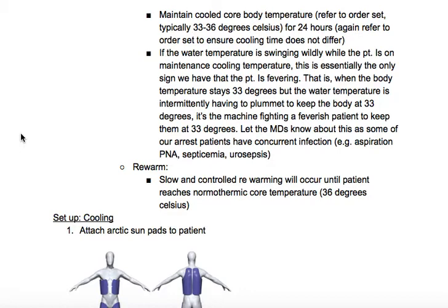And then this was another small note that Chris also made I thought was really interesting. Because the patient is febrile, or could be febrile, we're not going to know it because we are specifically cooling them. So once we get into the setup, I can show you on here where you can actually take a look at the water temperature, because the water temperature is what's going to adjust to make sure that the patient stays the desired temperature. Meaning if the patient starts to get too cold, the water temperature will heat up. If the patient starts to get too hot, the water temperature will cool down to keep the patient at a very steady cold body temperature.